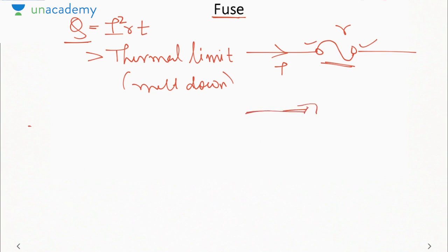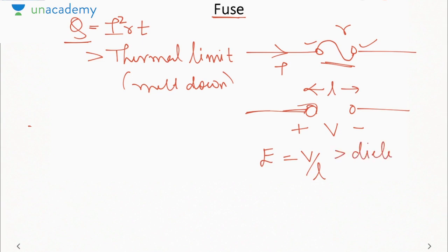There will be an open circuit in the system like this. Now the open circuit will have a certain voltage across it, and if L is the length, then the electric field will be equal to V by L. Now if this electric field is greater than the dielectric strength, then what will happen? Then the air between these two terminals will ionize, and if air ionizes, it will become conducting, so current will flow between the two terminals, and hence the purpose of the fuse will be lost, because the basic purpose was to disconnect the 2 points.